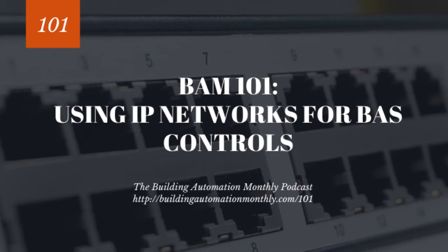When you look at a lot of this, you really want to put your infrastructure in first. Think of this case: the guys run the core infrastructure in a building, and that's great, and then you go do your tenant work. But there's no reason why you can't do all of your network infrastructure first, so when the tech lands on site, he plugs it into the controller and it works. You're not doing a power-up and communication commissioning after the fact, when all the equipment's landed and all the IT gear finally arrives. You can do it as you plug in the controller, commission it, make it work, close the door to the room, and you're done.